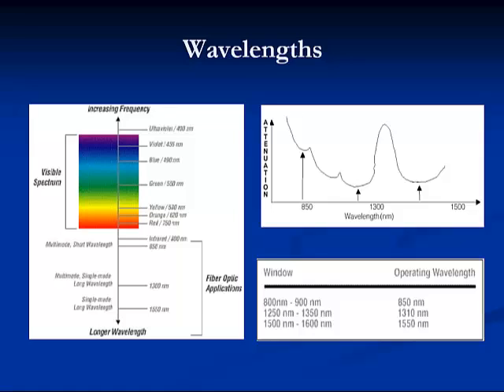There is significantly less attenuation loss at 1300 nanometers than at 850 nanometers. Specifically, multi-mode fiber operates at both 850 nanometers and 1300 nanometers, while single-mode fiber operates at 1310 nanometers and 1550 nanometers.